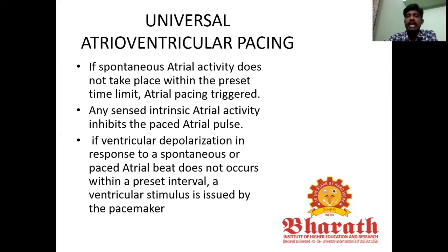If spontaneous atrial activity does not take place within the preset time limit, atrial pacing is triggered. Any sensed intrinsic atrial activity inhibits the paced atrial pulse.